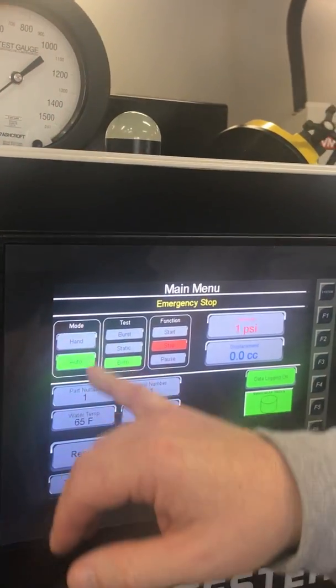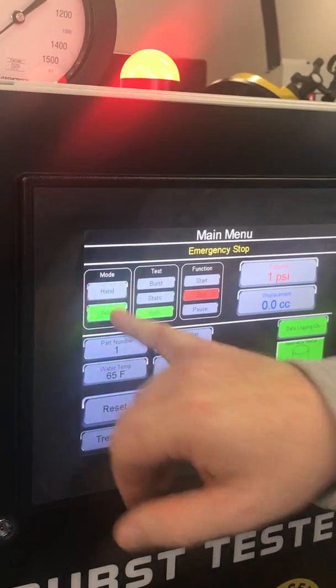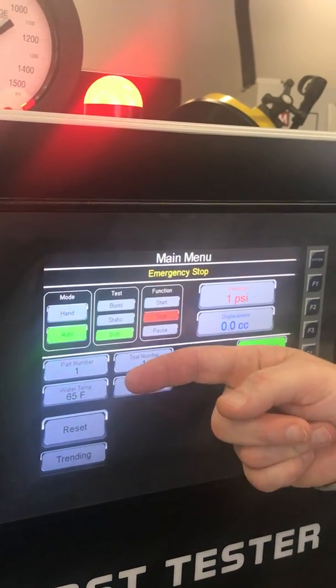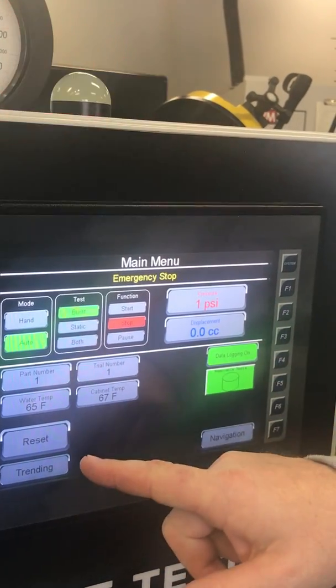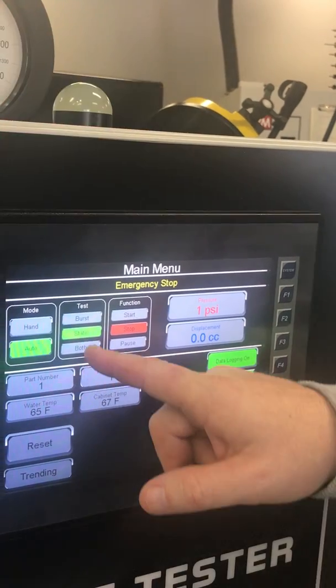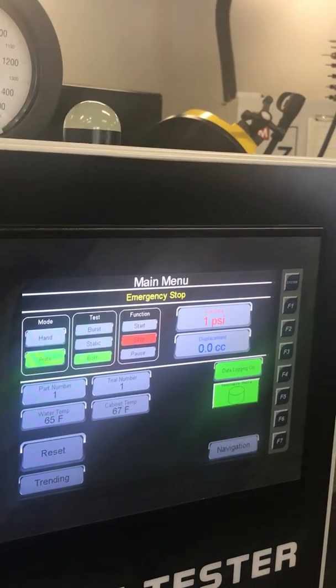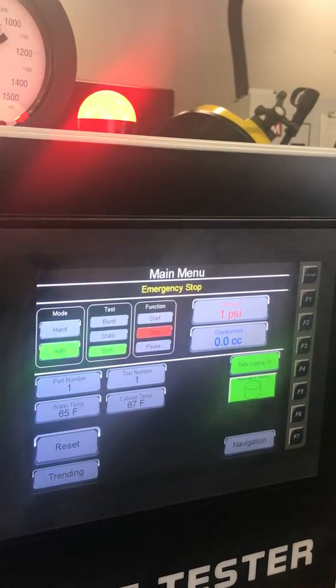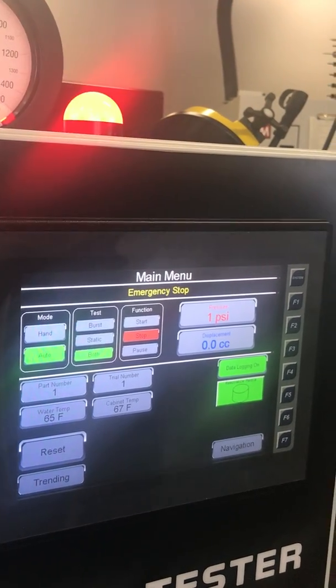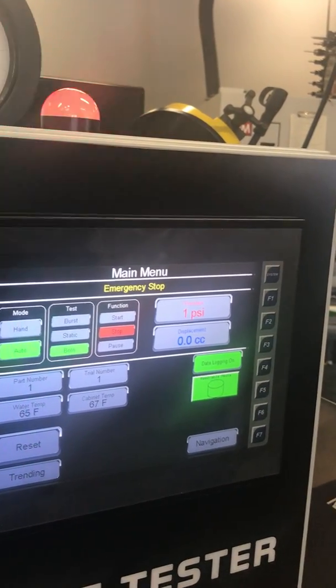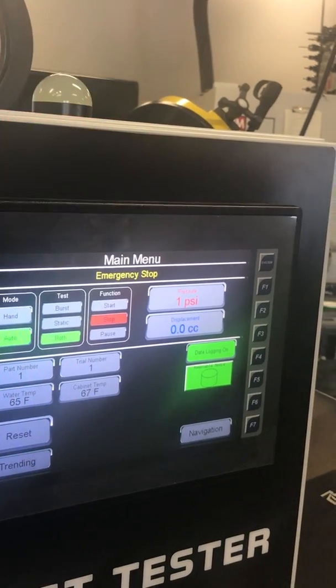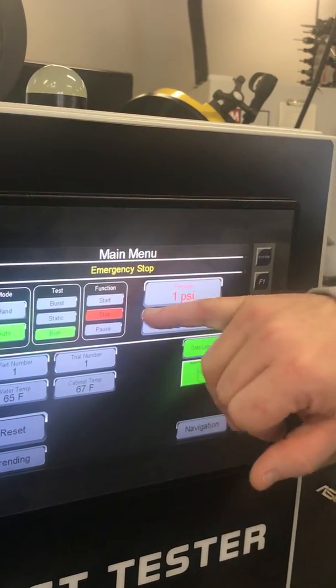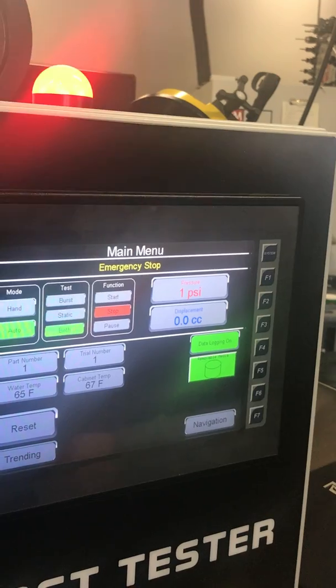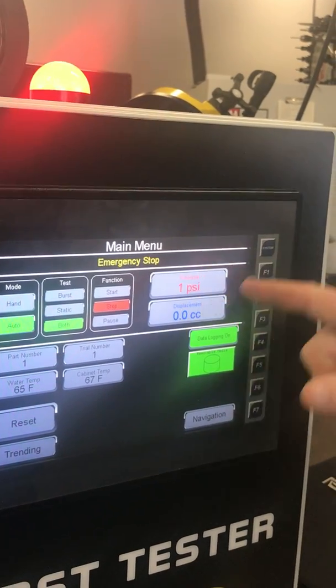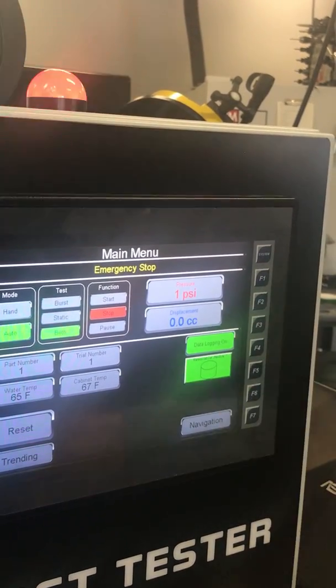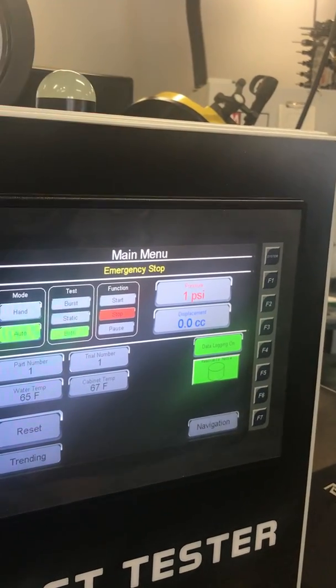So you've got modes, hand and auto. Which test would you like to run? A burst test only, a static test only, or both? When both is selected, it's going to do a static and then a burst. I don't think it would do much good to do the burst and the static if you blow a part up. Right, exactly. And then the function, you've got a start, a stop, and a pause. Here we're displaying the actual pressure in the system, and then the displacement in cc's.